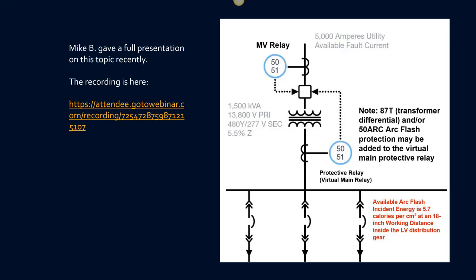So now we've eliminated a piece of hardware that we need to maintain. We've shrunk our real estate by at least 30 inches. Again, depending on the ampacity of the main itself, how much space you'll be saving. You'll always be saving some, but the larger the ampacity, the larger the transformer, the larger the secondary breaker, the more space you're going to save. And now we've moved our lockout tagout point for the substation to that primary device.